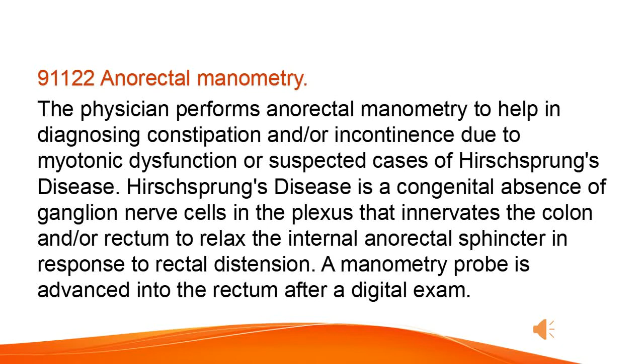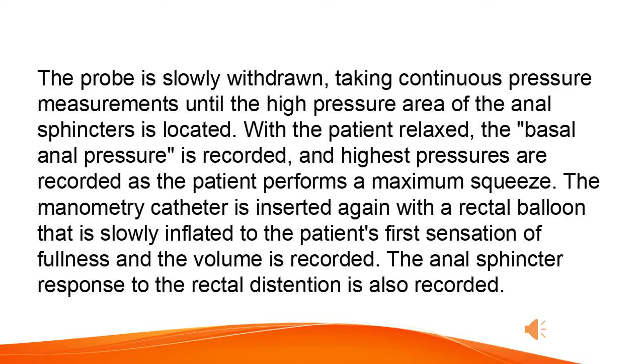The probe is slowly withdrawn, taking continuous pressure measurements until the high pressure area of the anal sphincters is located. With the patient relaxed, the basal anal pressure is recorded, and highest pressures are recorded as the patient performs a maximum squeeze. The manometry catheter is inserted again with a rectal balloon that is slowly inflated to the patient's first sensation of fullness and the volume is recorded. The anal sphincter response to the rectal distension is also recorded.